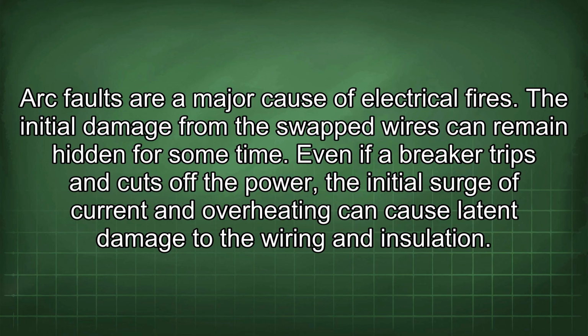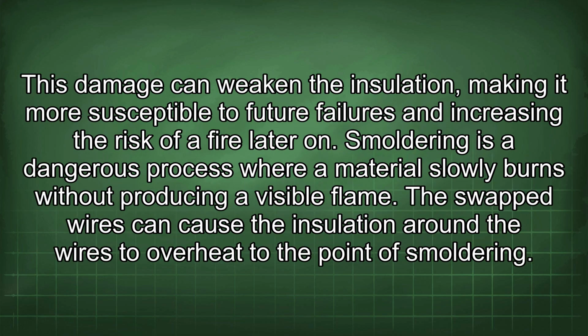The initial damage from the swapped wires can remain hidden for some time. Even if a breaker trips and cuts off the power, the initial surge of current and overheating can cause latent damage to the wiring and insulation. This damage can weaken the insulation, making it more susceptible to future failures and increasing the risk of a fire later on. Smoldering is a dangerous process where material slowly burns without producing a visible flame.